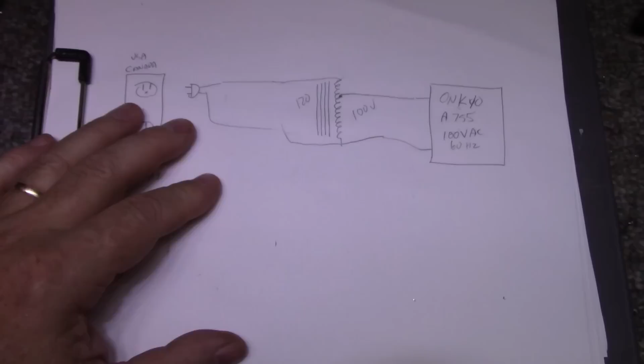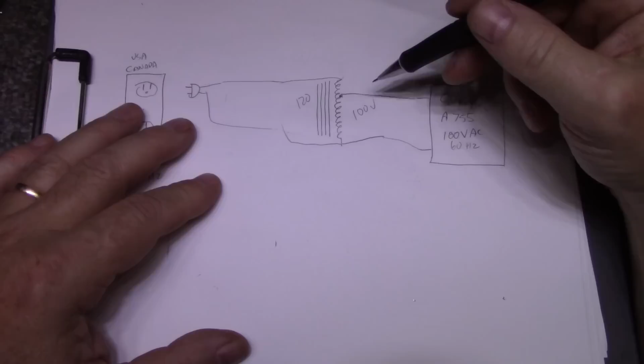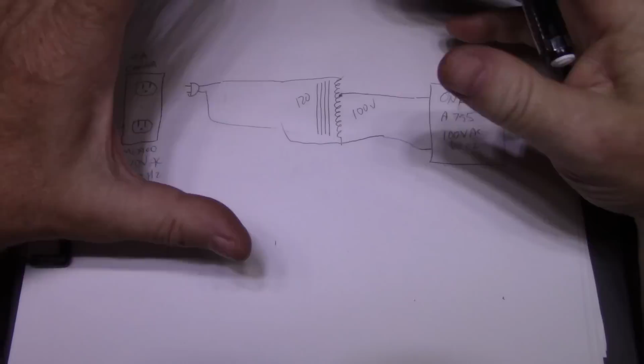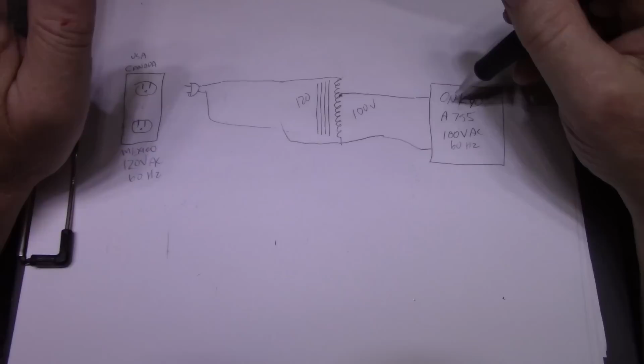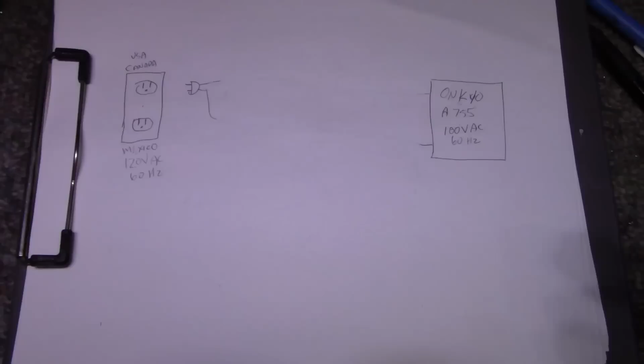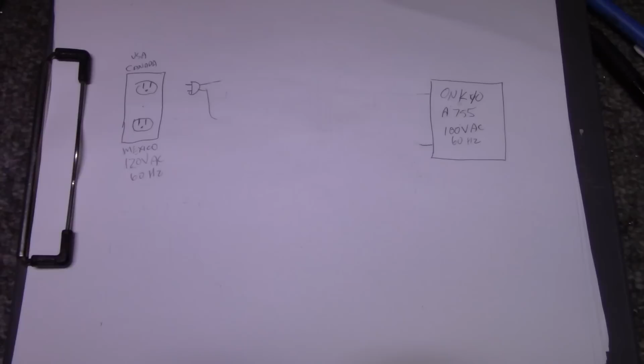Trying to find an auto transformer with the correct rating, you probably could find them, I don't know, I haven't seen them out. You'd probably have to get one custom wound. This would probably be a little smaller than regular transformers, because you're dealing with one less winding, so they have a smaller physical size, and might be sized small enough to fit inside the amplifier, but I kind of highly doubt it. So that's another option. What I forgot to mention is, with the auto transformer, you're probably going to have better regulation than just a regular transformer. So that's the positive there.